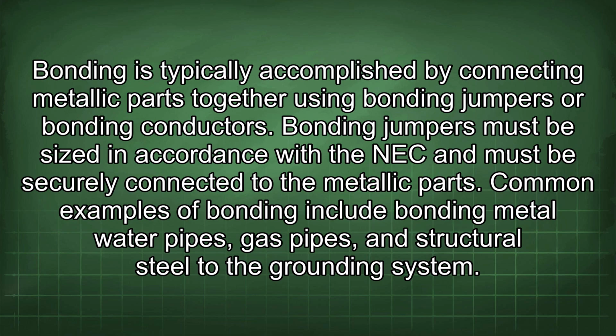Bonding is typically accomplished by connecting metallic parts together using bonding jumpers or bonding conductors. Bonding jumpers must be sized in accordance with the NEC and must be securely connected to the metallic parts. Common examples of bonding include bonding metal water pipes, gas pipes, and structural steel to the grounding system.